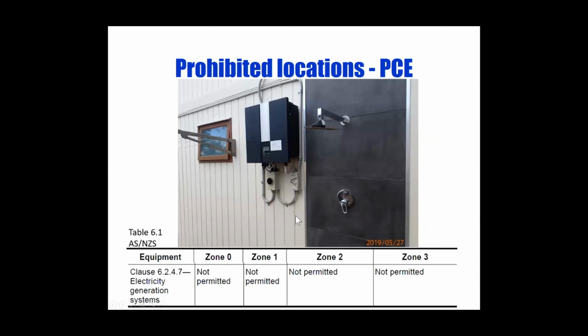This is a great photo that I took quite some time ago now, last year. I wish I actually took a step back and took a photo of what was next to it. It was actually right next to a pool as well. Essentially, what we're trying to get at here is if an inverter, or I should say an electricity generation system, is in a damp situation zone, it's not permitted. And this is just an extract of AS/NZS 3000, table 6.1, and it's showing zone 0 through to zone 3 is not permitted.